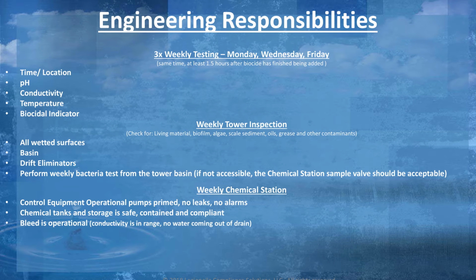We recommend Monday, Wednesday, and Friday at the same time and an hour and a half after biocide has finished entering the system. The items that you must record are time, location of sample, pH, conductivity, temperature of the system, and the biocide indicator. This must be logged in the logbook under the specific time and day in Section 2. There can never be more than 2 days in between each test.